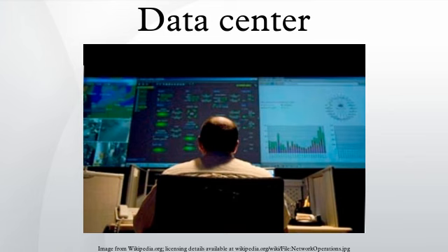Energy use. Energy use is a central issue for data centers. Power draw for data centers ranges from a few kilowatt for a rack of servers in a closet to several tens of MW for large facilities. Some facilities have power densities more than 100 times that of a typical office building. For higher power density facilities, electricity costs are a dominant operating expense and account for over 10% of the total cost of ownership of a data center. By 2012, the cost of power for the data center is expected to exceed the cost of the original capital investment.